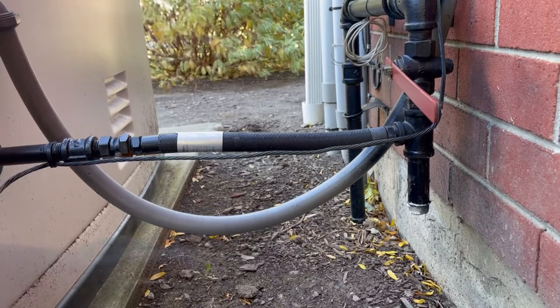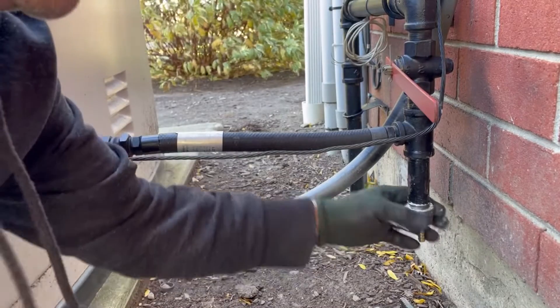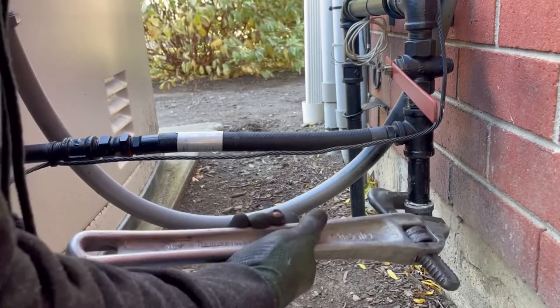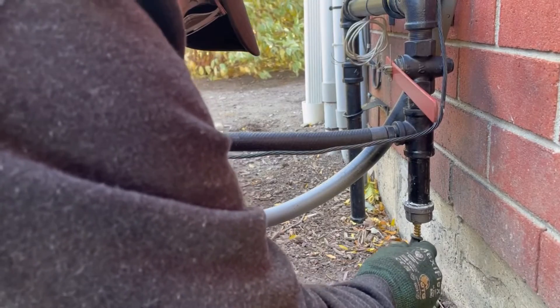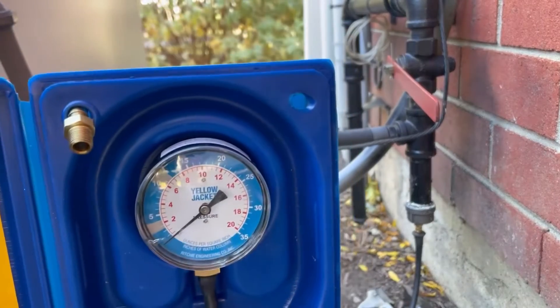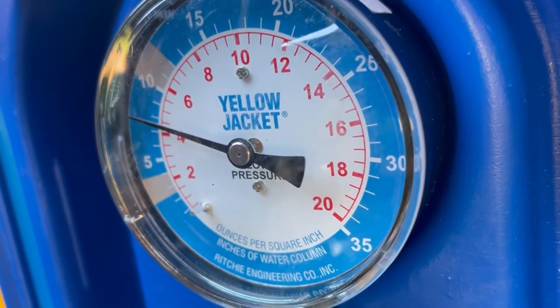When removing the cap always use two wrenches — one to hold the nipple from turning and the other to remove the cap. Put a bit of pipe dope on the threads and install the adapter. You don't have to tighten it too much, it's not a permanent connection. We're only talking about a quarter of a pound of pressure. With the test cap on, attach the manometer. The static test pressure is 7.5 inches water column. Perfect.